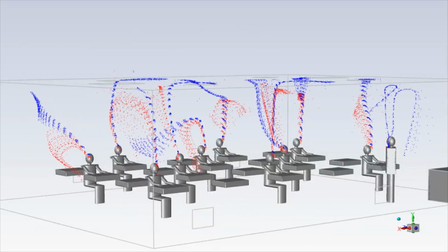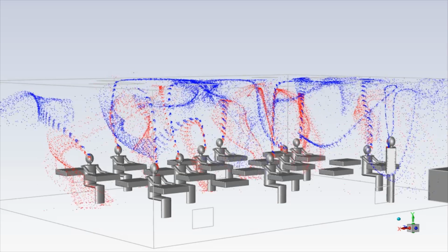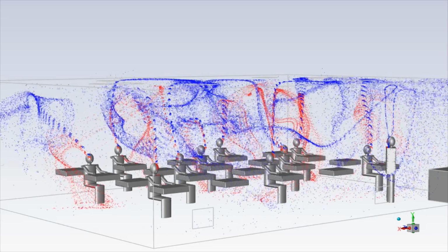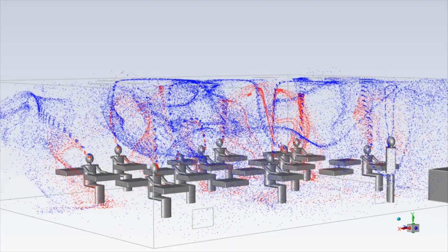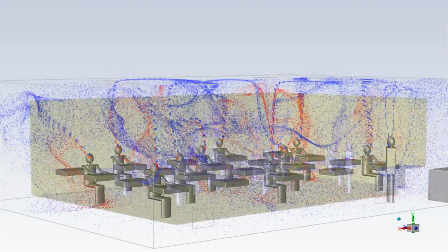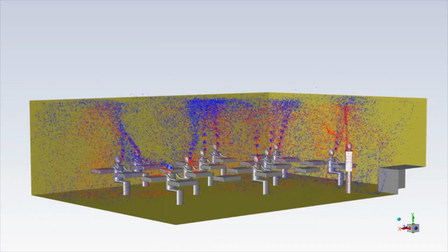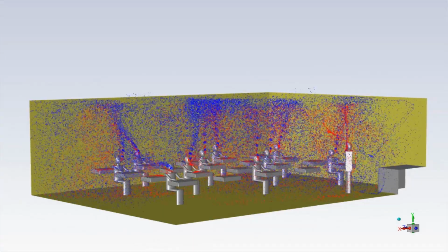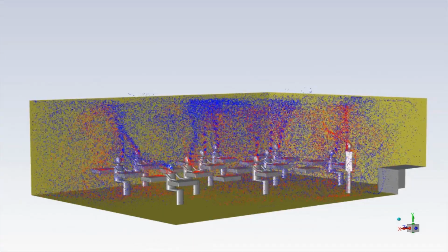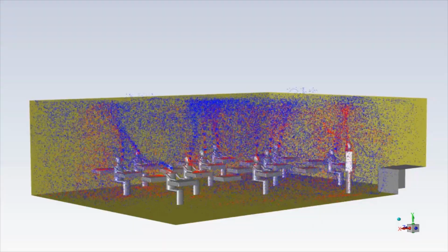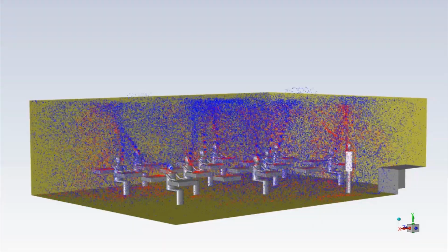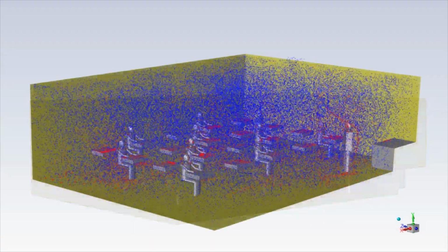Note also these simulations use the equivalent of 100% fresh air, that is, no particles entered the space with the ventilation air. In conclusion, reducing indoor hazards, both biological and chemical, would require a revolution in ventilation practices that changes the top-down mixing system to something that moves the air uniformly through the space, with reduced mixing and recirculation.